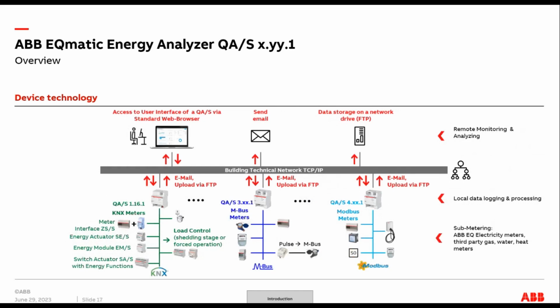If we look at the device technology and what we're typically sitting on our TCP network, we're going to have our 3 EQmatics connected, as you can see there. Starting on the right, you'll have the Modbus meters connected to the QAS4. This device will take any Modbus meter you want. The Modbus register mapping is done for all the ABB meters. However, if you want a non-ABB meter or a different meter connected to it, you can create your own meter instance, define the mapping for that, and use it throughout your project.